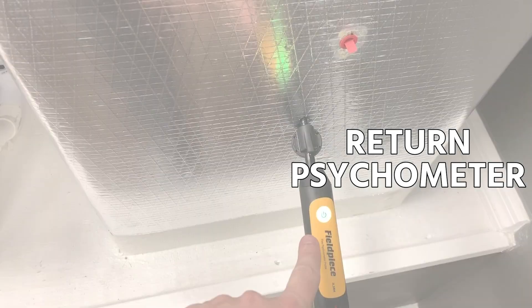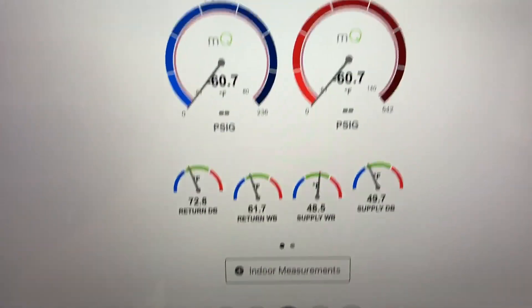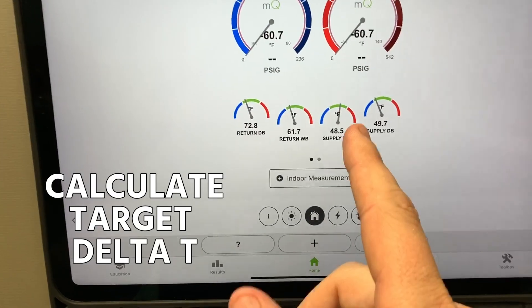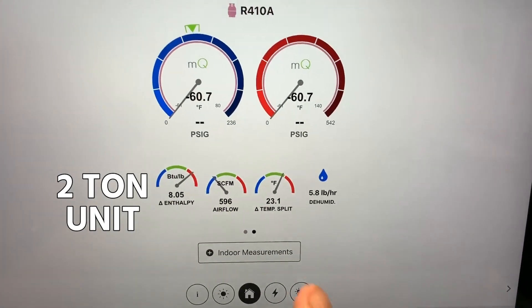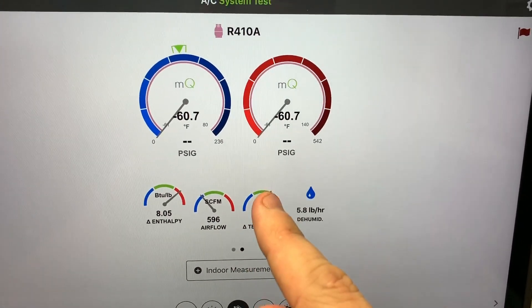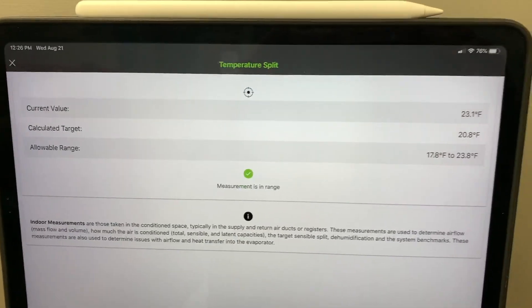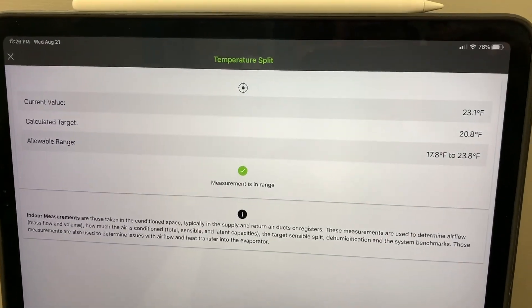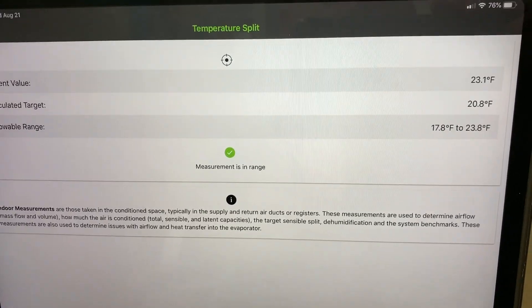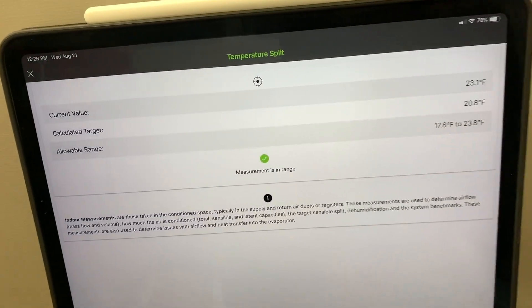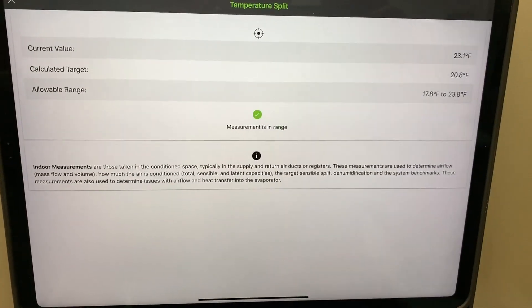With one psychrometer on the return and one on the supply, you get return dry bulb, return wet bulb, supply wet bulb, and supply dry bulb. There are universal charts to help calculate target delta T, but with a variable speed unit running lower airflow per ton — this is a two-ton unit — the target is showing as 20.8 because MeasureQuick is normalizing for system capacity given current conditions. Most universal charts figure 400 CFM per ton and standard operating conditions, and this equipment won't produce the same capacity in real field conditions.